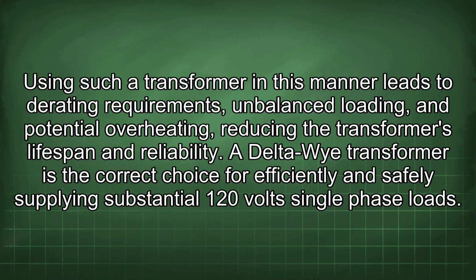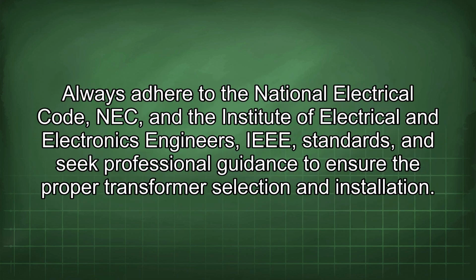Using such a transformer in this manner leads to derating requirements, unbalanced loading, and potential overheating, reducing the transformer's lifespan and reliability. A Delta-Wye transformer is the correct choice for efficiently and safely supplying substantial 120 volt single-phase loads. Always adhere to the National Electrical Code (NEC) and the Institute of Electrical and Electronics Engineers (IEEE) standards, and seek professional guidance to ensure the proper transformer selection and installation.